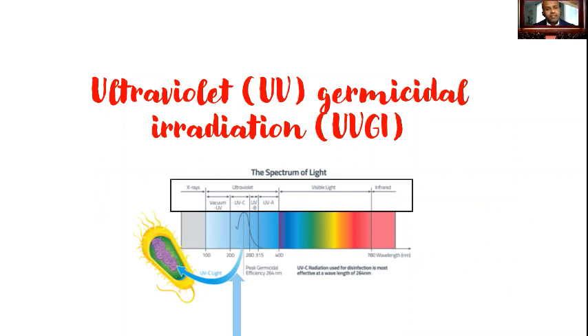UVGI is another disinfection method that uses UV light, the UV radiation, to inactivate microorganisms so that they're unable to reproduce and potentially cause the disease. So as you may know, the UV light belongs to the electromagnetic spectrum with a wavelength in the range of 200 to 400 nanometers, which is invisible to the human eye. The UV spectrum can be subdivided into a few subcategories, like UVA, UVB, and UVC. So UVC is the one that we are talking about here.